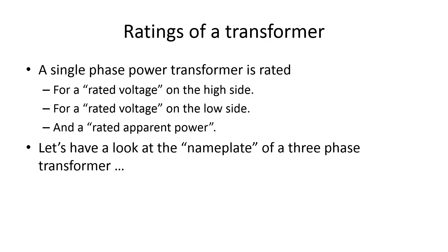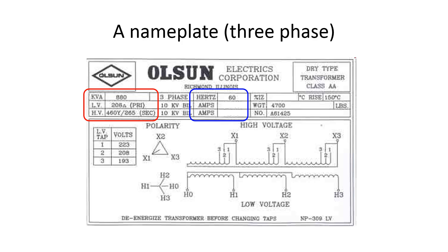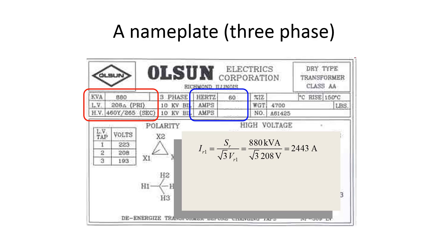Let's have a look at the nameplate of a three-phase transformer. We see the rated power, the rated voltage for the low side, and the rated voltage for the high side. Because it's a three-phase transformer, those voltages are line-to-line for the low side and both line-to-line and line-to-neutral for the high side. The primary is connected in a delta and the secondary in a star.